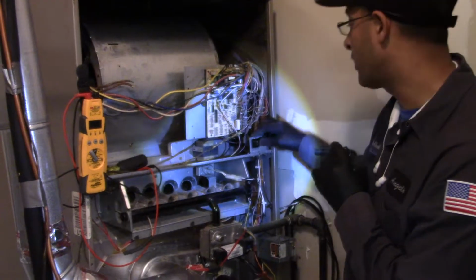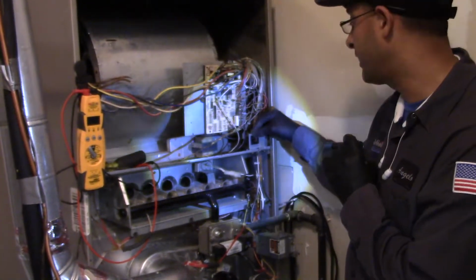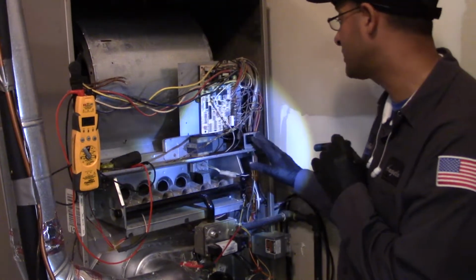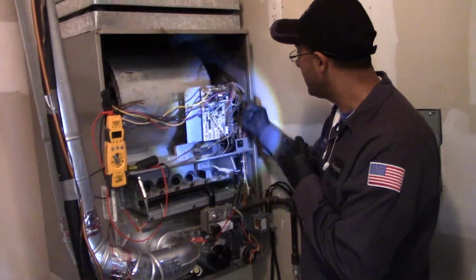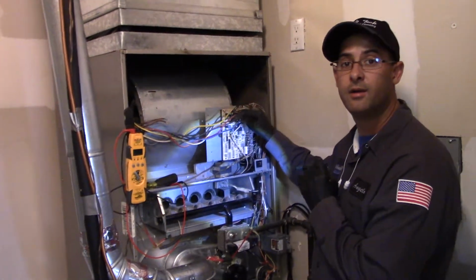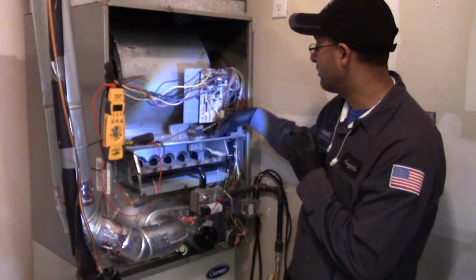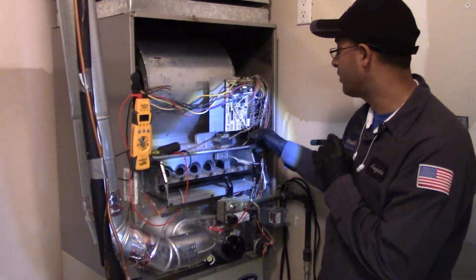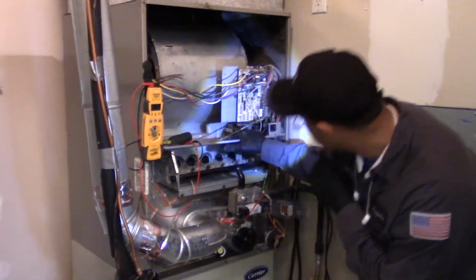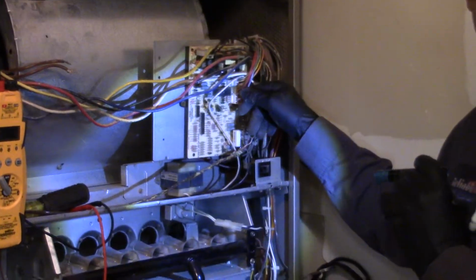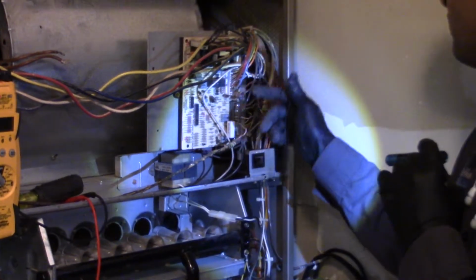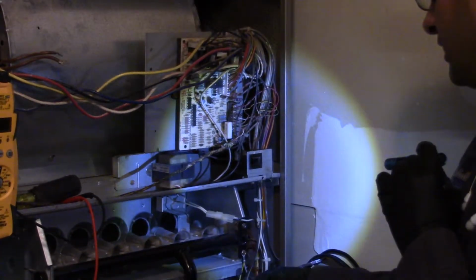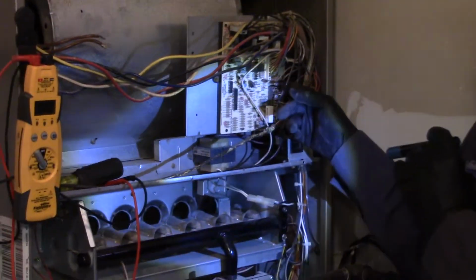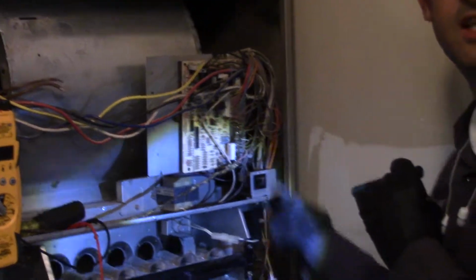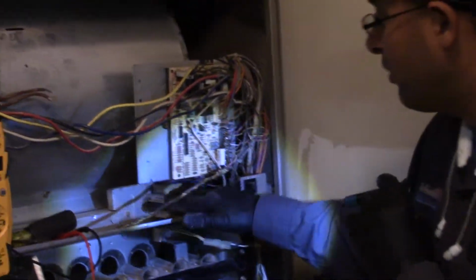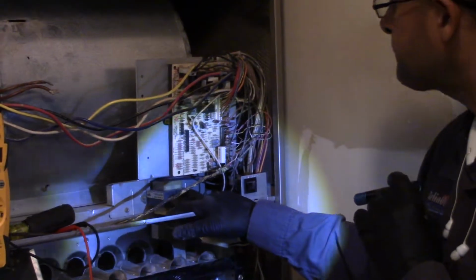When it's closed, or if we're working on it, I can put some tape on here or something to hold it. And I believe they sell magnets that will actually hold it for service guides. So power will run through here, and then after this goes into the board. And then from the board, that's when it runs through the transformer as well, for the 120 volts. And then it comes out of the transformer, 24 volts back into the board. And it feeds the board the 24 volts. You know, so you have your LED and you have your limit switches and stuff there. But it also mainly allows the thermostat to take that 24 volts and send it back to the relays. Okay, that's just an example of where that transformer is.